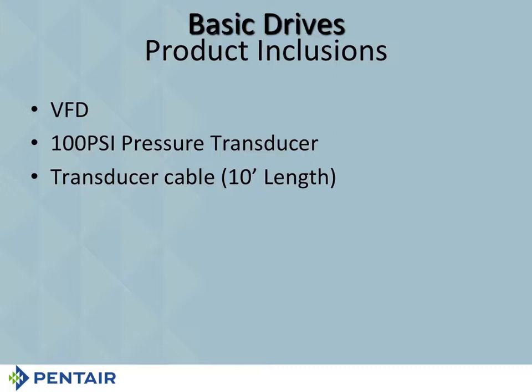If you've got, say, for example, you're 20 feet away from the drive with your transducer, buy a 50-foot and cut it down. Now, don't cut it too short, but cut it so you don't need that extra 30 feet. You don't want to wind it up and save it. Just cut it and get rid of it. But you just want to make sure that you're not splicing the cable, because that's bad. It's very difficult to get that spliced.